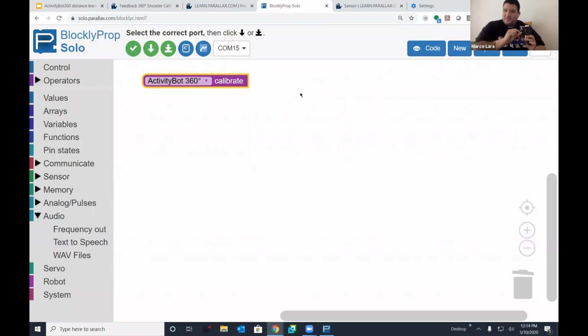Well, only for the download, for the download or for loading the program, you'll need the switch to be in position 1. Okay, so I'll turn it off, turn it back on, position 1, searching, COM3, came back up, load and run. It's working now. Oh good. And then after it says completed, turn it. Position switch to 0, put the switch on 0. Okay, and disconnect, and then put it on the ground and turn it to 2.